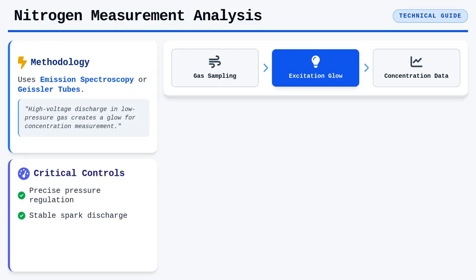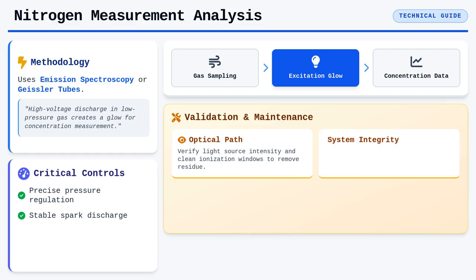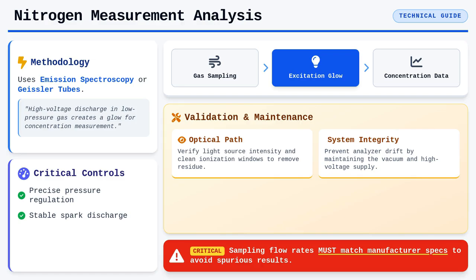You will encounter physical optimization routines that require periodic validation of the light source intensity and the integrity of the ionization window, which can become clouded by residue over time. Any analyzer drift in these systems can lead to systemic errors in ventilation distribution calculations. So maintaining the integrity of the vacuum system and the high-voltage supply is non-negotiable. Always verify that your gas sampling flow rates match the manufacturer's technical specifications, as any deviation here can invalidate the ionization mechanics and lead to spurious results.